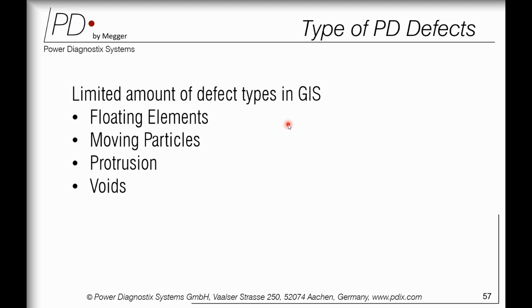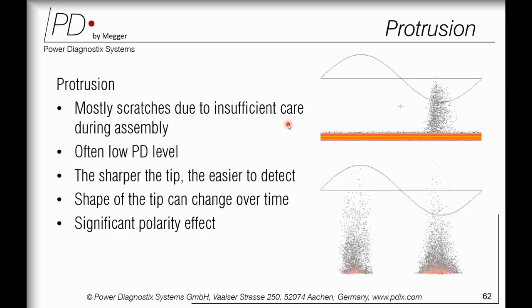So these are a few PD patterns I would like to show in the upcoming slides: floating elements, moving particle, protrusion, and voids. This is one of the slides of protrusion. This is a single protrusion. Here you have multiple protrusions. Protrusion means sharp edges, mostly scratches due to insufficient care during assembly. Often it has a very low PD level, but the sharper the tip, the easier to detect, because it creates more PD activity and electromagnetic waves. The sharpness of the PD tip can change over a period of time, so you might have a significant polarity effect as well.